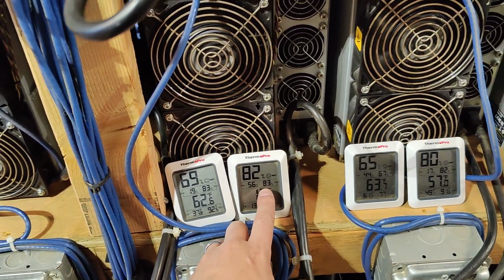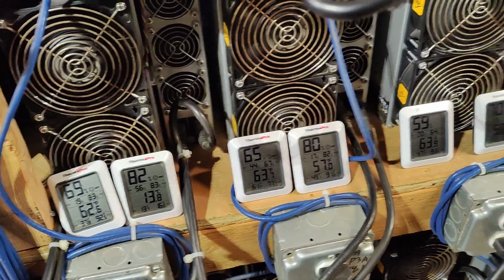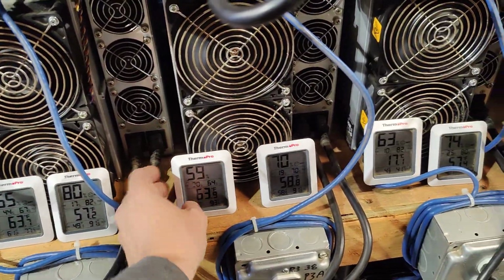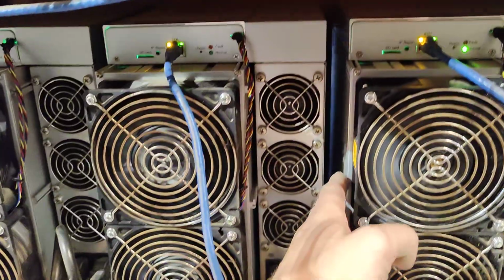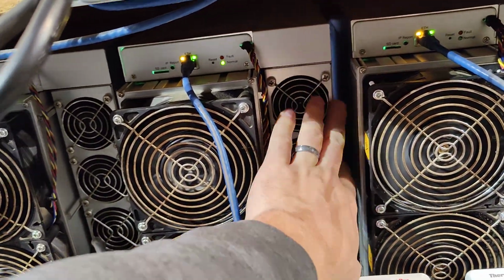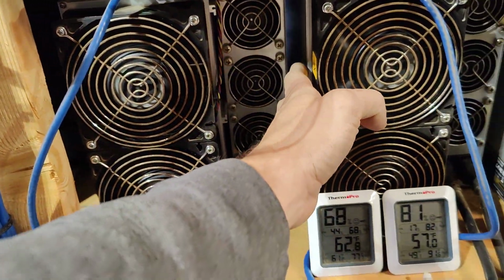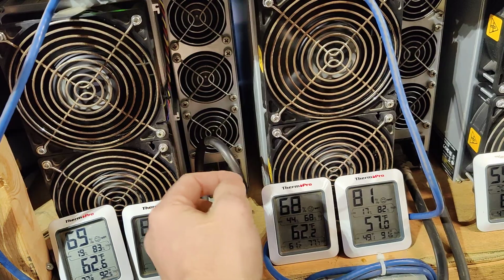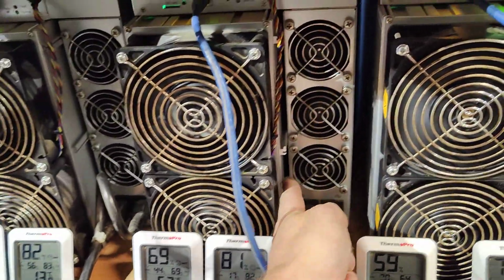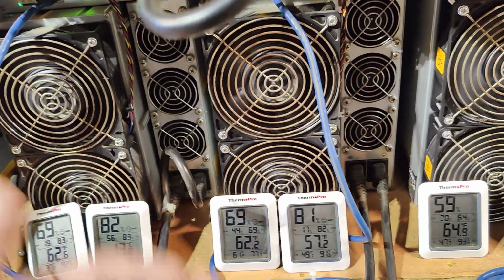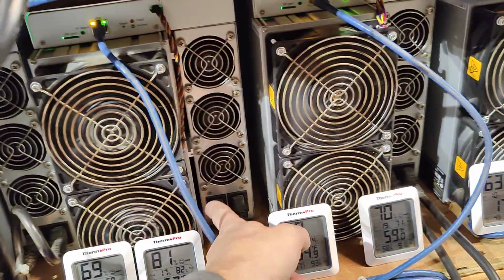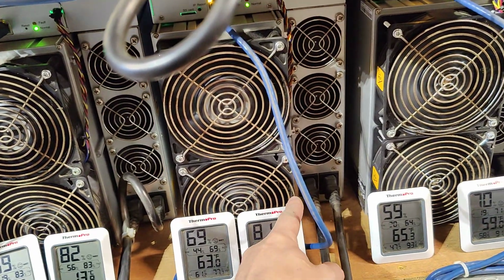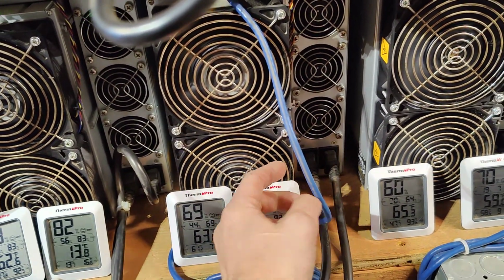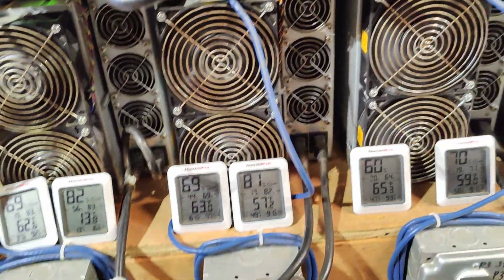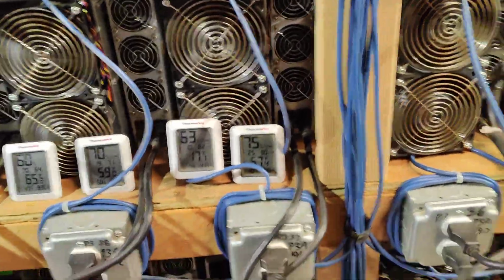So we can see we're getting 82% here, 65, 80. I put the humidity sensors right next to each other because we got hot air coming in between the miners here. I did this, I put this crack here on purpose, make sure the hot air wraps around and gets sucked in on the sides. Same thing over here, and obviously you have that crack that comes with every miner, which is good. We want that hot air to also go through that little crack and then get sucked into this edge of the miner. So these two edges are being supplied with warmer air. That's what we want. Basically, I checked this whole section here from the top to the bottom.